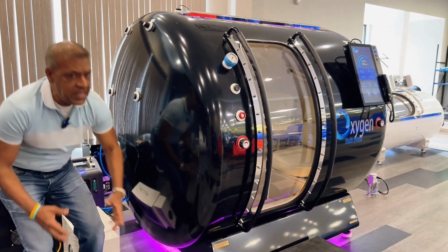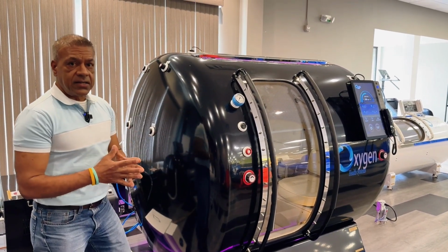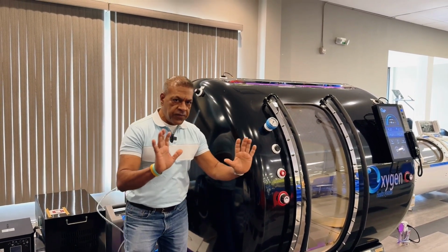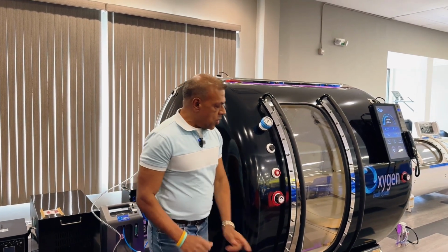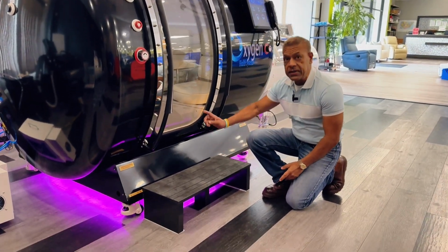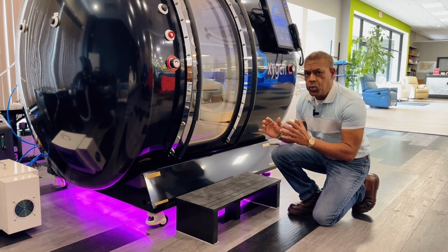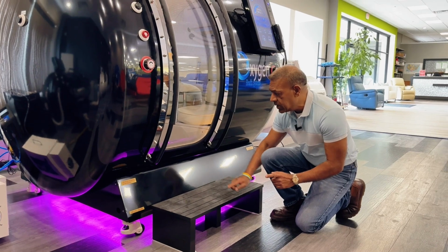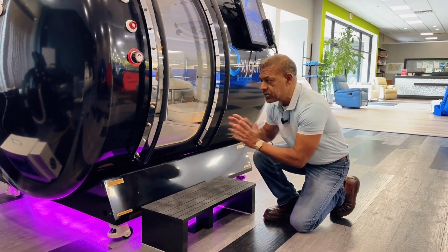Now let's move here, take a look at the profile of this machine, which is very low profile, and that would prevent any possible psychosomatic response or claustrophobia. It is engineered in such that having this low profile gives you the impression from inside that you are not cooped up in a small confined area. Also, take a look at this stepping stool. With this low profile, when you step on this stepping stool, individuals with range of motion challenges would not have any issues whatsoever simply by taking advantage of this stepping stool and then having this much area to go over in order to get into the chamber.